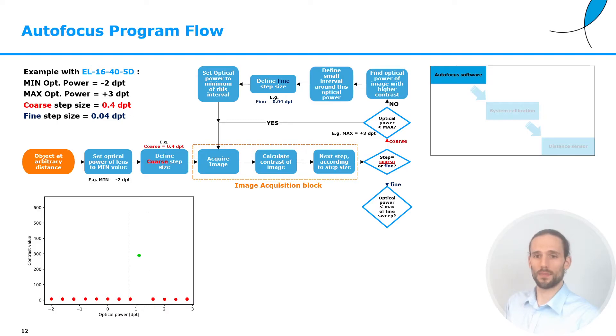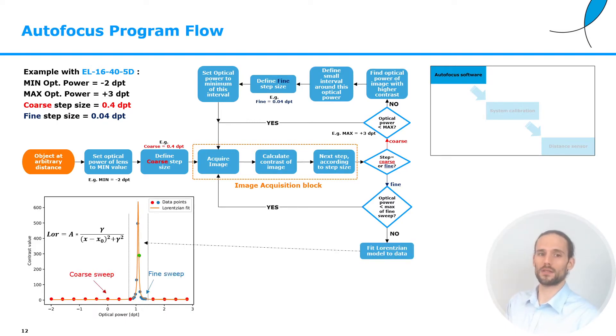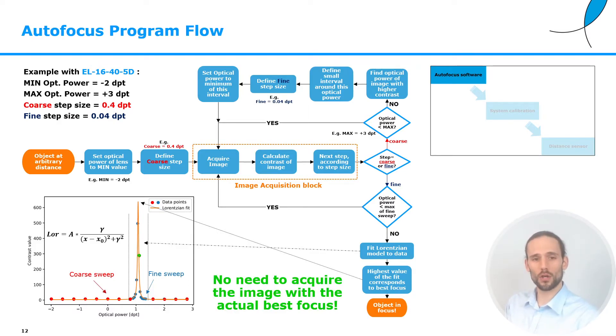And we will go again through the image acquisition block. Similar as before, we will basically now check whether the step size is fine or coarse. And of course, at this point, we are in the fine step size regime. And we will check again whether the optical power is smaller than the maximum optical power we have defined for the fine sweep. In case this is true, we will go again and again through the image acquisition block. At the point where the optical power now is bigger than the max of the fine sweep, we are basically done. We will plot all the points that we have acquired and we will fit a Lorentzian model to this data. The maximum of this Lorentzian curve will be the best focus. Now we can move the lens to that specific optical power and we will have our object in focus. I want to point out that the power of this approach is that one does not need to acquire the image with the best focus, but this is given by the maximum of the fit.